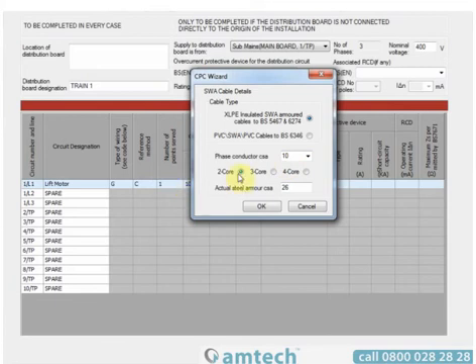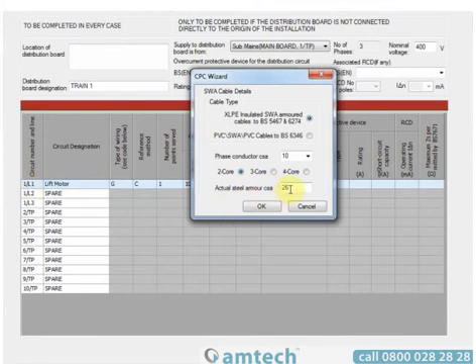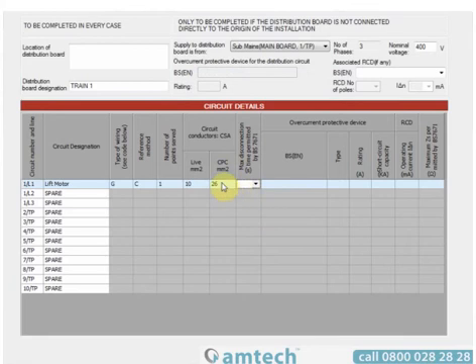It's also selected the phase conductor size of 10mm because we pre-selected that in our live CSA section, and pre-selected 2-core on the assumption that it's a single phase. It then gives us the actual steel armor CSA, and on selecting OK that will populate that field. If you don't wish this to appear, you can type any value you wish, including letters.